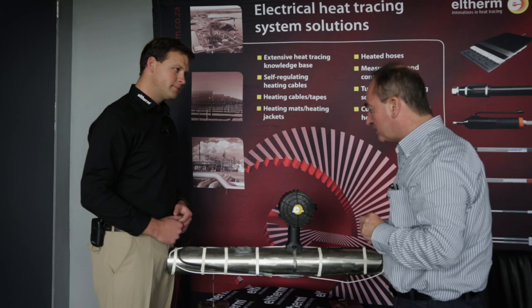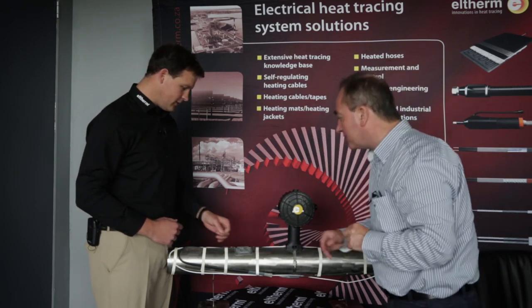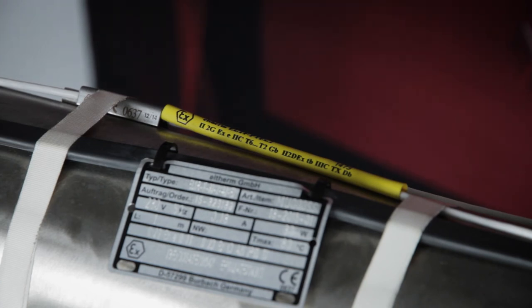Great, and Giles, what can you tell me about this particular yellow cable here? So what we have over here is an example of the nameplate we mentioned previously, and an example of an explosion-proof area RTD sensor, which is a thermal device used to transmit the temperature back to a transmitter, and that's recorded by your client on whatever platform he has chosen. The RTD sensor is mounted on the pipe, or it can also be mounted next to the cable depending on what temperature you're looking to get. It's an important part - when you're talking about your serial cable, your constant wattage cable, and your mineral insulated cable, they'll have to have some form of RTD.